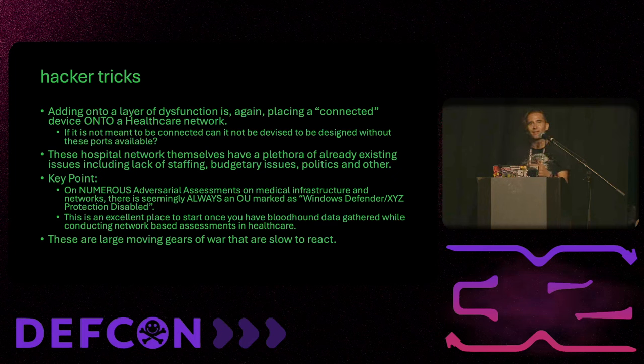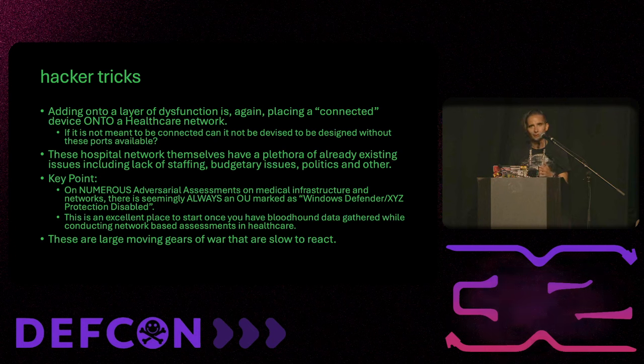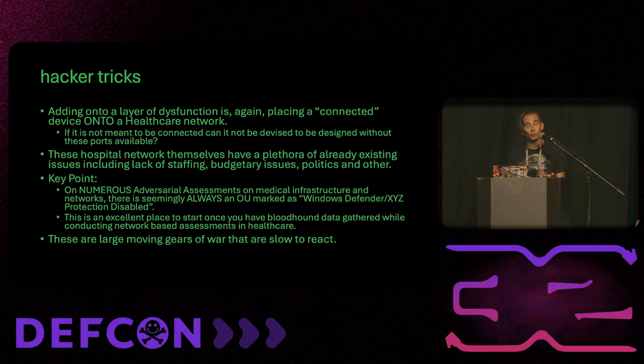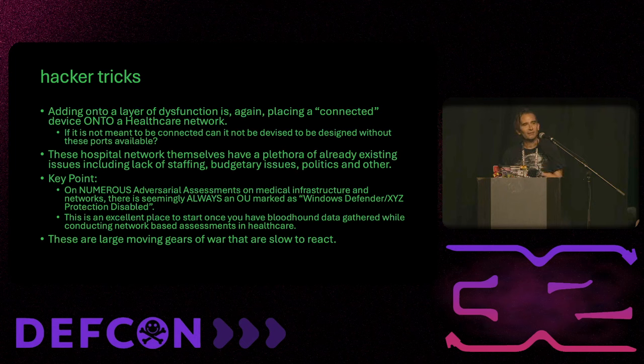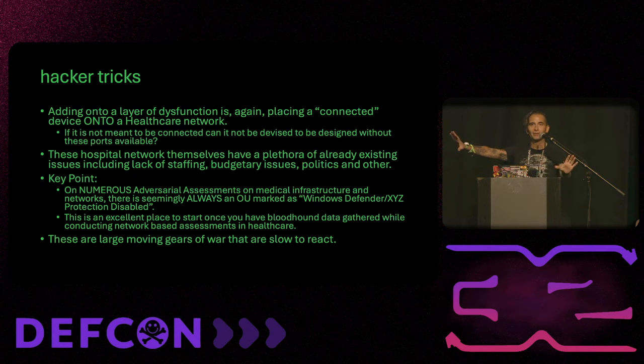Another layer of the dysfunctional reality is that placing these connected devices onto the hospital network increases risk. If it's not meant to be connected onto the network, I still don't know why they put networking on these. Most of the time what I hear is that the developers for the boards are just utilizing what's there, and sometimes that has Wi-Fi. They just don't know how to disable it, or they'll just leave the chip on there. If it's not needed and it's not supposed to be plugged in, then don't keep the stuff in there. Just put some glue in the port and make sure nothing goes in — a soldering iron can do this. But they put in big words saying don't plug this into the network, but here's a network jack.